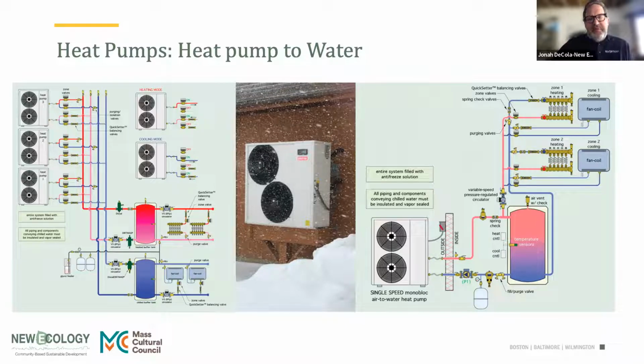So this is another alternative. We have a self-contained appliance that's on the outside of the building, and it has its own refrigerant in it, but it puts its energy directly into water. And so we're looking at a couple of piping schematics where we have water being taken to the outdoor unit. The energy of the outside air is being put into it, and then it's being distributed into the building. And that can be distributed into what we call fan coil units. So it can be both cooling and heating, depending on what the load is. Now, the graphic on the left is a little bit more complicated for, say, a larger building that might have both cooling and heating needs at the same time.